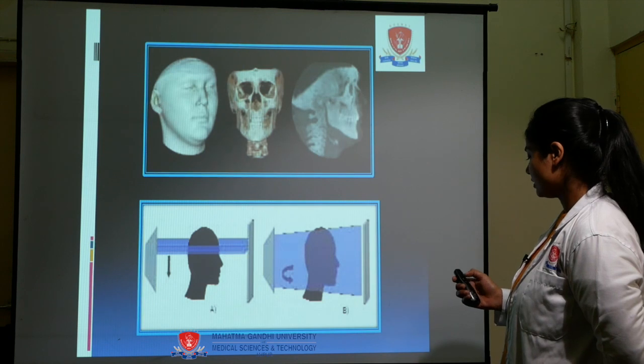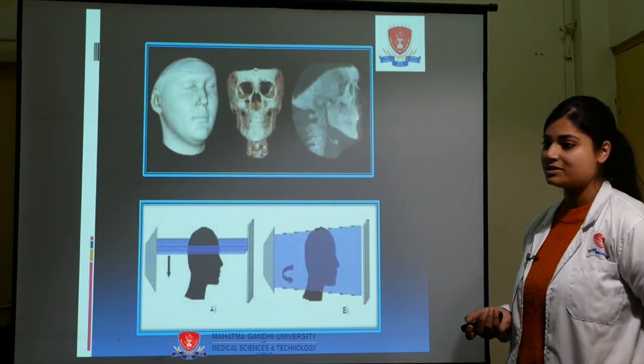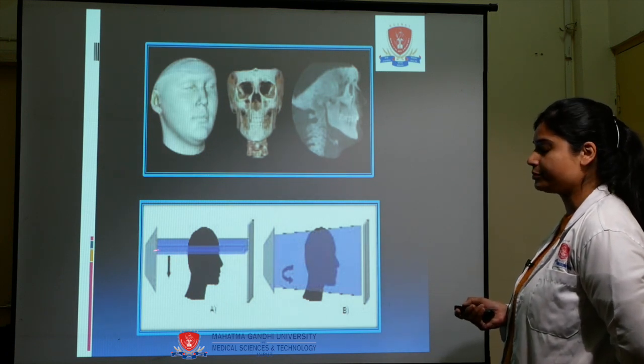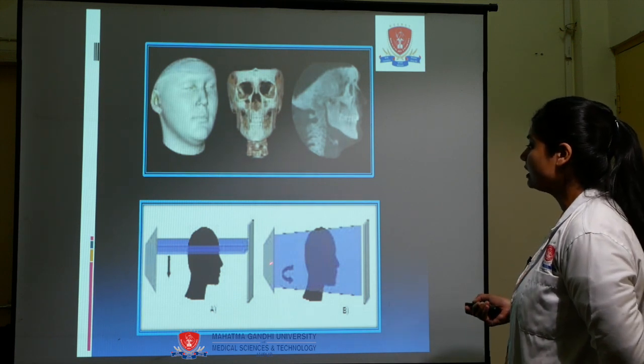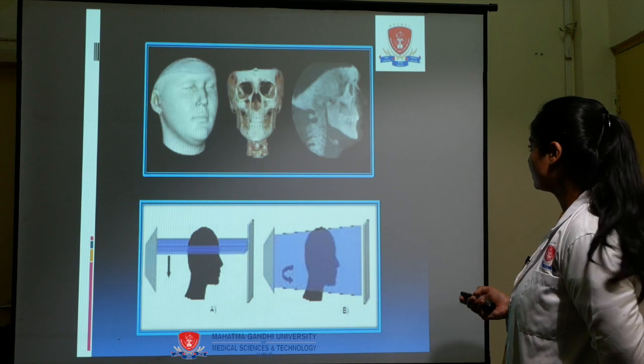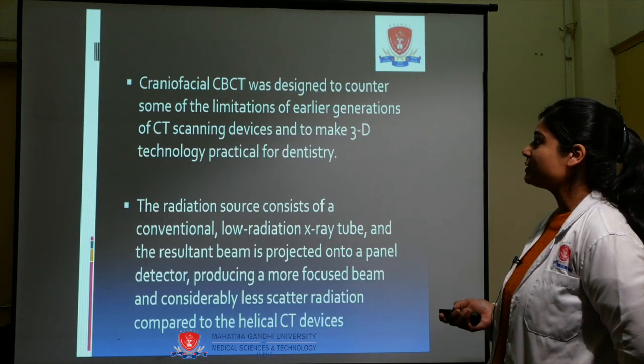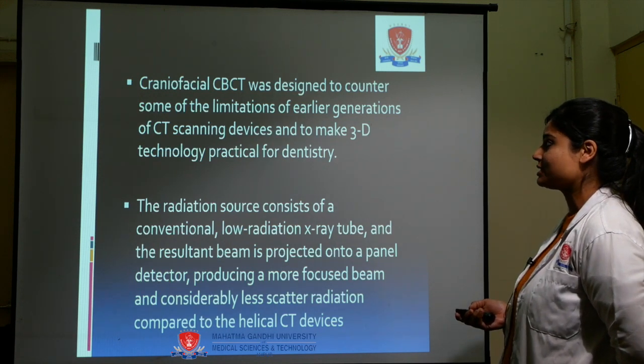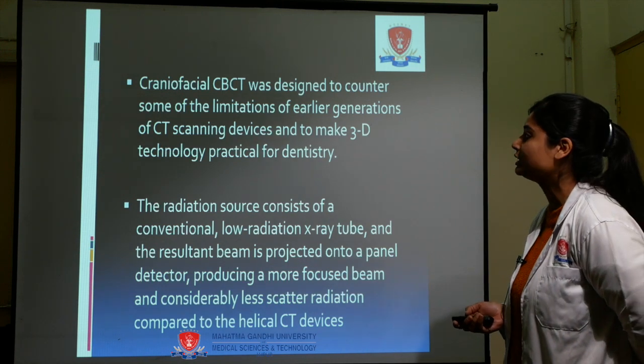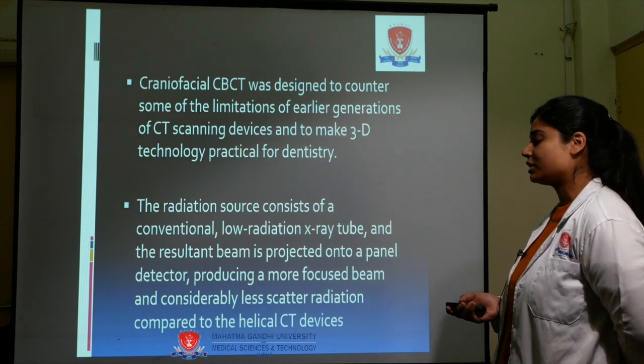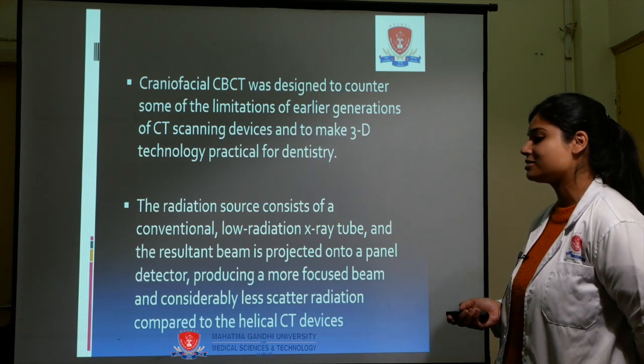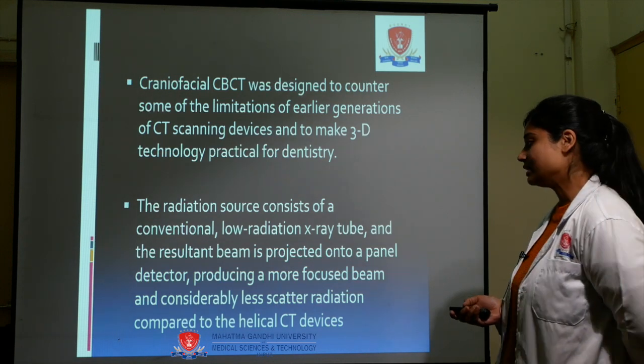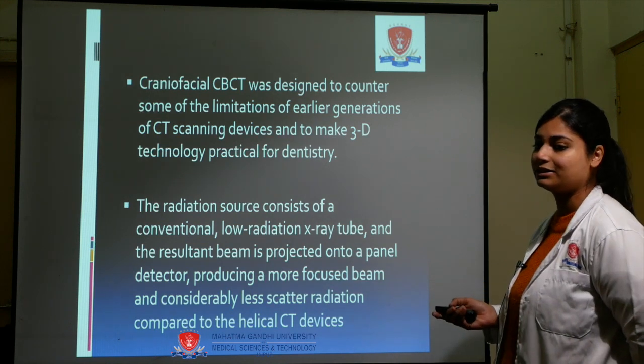The main difference between CT and CBCT is that in CT, a fan-shaped beam is used, whereas in CBCT, a cone-shaped beam is used. Craniofacial CBCT was designed to counter some of the limitations of earlier generations of CT scanning devices and to make 3D technology practical for dentistry. The radiation source consists of a conventional low-radiation X-ray tube, and the resultant beam is projected onto a panel detector, producing a more focused beam and considerably less scatter radiation compared to helical CT devices.